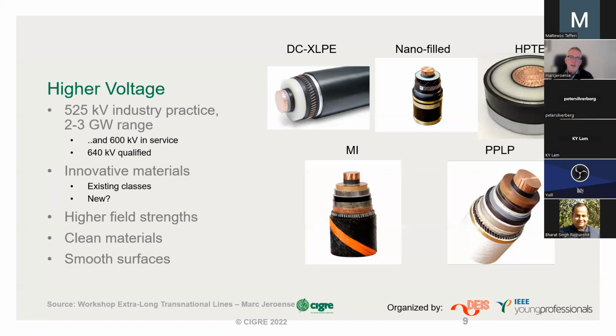But in future, I'm sure that we will see, when we leave the sweet spot of 525 kV, higher voltages, which will need higher field strengths, and which come also with an extreme need for cleanliness - not only physical cleanliness, but also chemical cleanliness. In terms of AC cables, we are always afraid of protrusions and dust particles or metal particles inside the insulation, which will create field enhancement. That is dangerous for AC cables. That is also dangerous for DC cables.